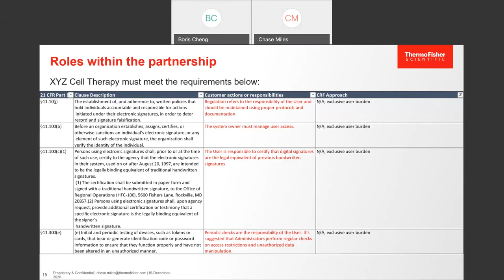Now, as a Cryomed manufacturer, it's not my responsibility to tell my customer what type of process they need or how to establish it - that's up to the customer site and their QMS system, but they'll provide that justification. Similarly, when I ship a Cryomed unit out, how the end user uses it at that point is up to them - they're going to have to create a process for managing users' access to the unit. So you can see there are some things that apply only to the XYZ Cell Therapy Company, while there are other things that apply only to the Cryomed manufacturer.